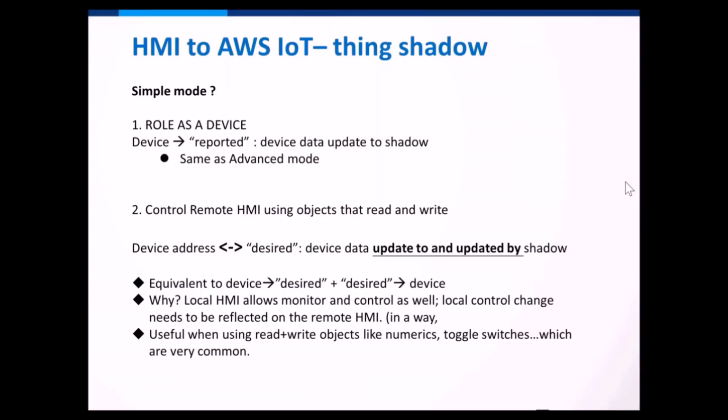So our local device cannot really reflect that, or we might actually overwrite the data we already wrote. This could cause very strange behavior of our HMI's objects, especially, like I said, numeric inputs or toggle switches, which use both read and write of the same address on the same object.